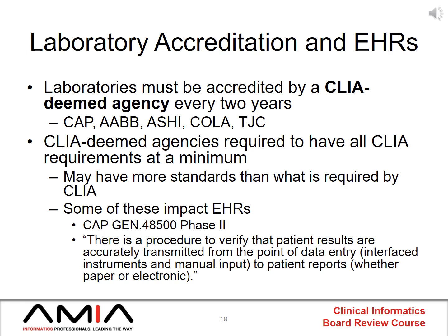So, for example, in the College of American Pathologists standards for the general laboratory, there's a phase 2 standard, and phase 2 is sort of the highest level of deficiency if you can't answer this standard appropriately. It requires a procedure to verify that patient results are accurately transmitted from the point of data entry to patient reports, whether they are paper or electronic.